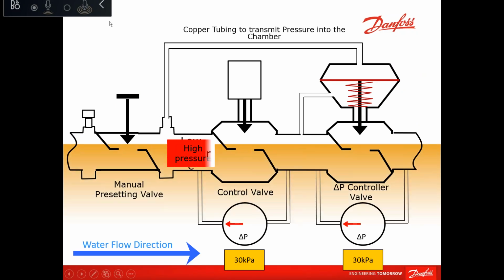And simply, what I was talking about is this part. This copper tube is linked directly with the pressure chamber. Another tube is linked with the lower pressure chamber. So if the pressure is high, it will go through here and push this part to close. Now look at the DPCV part, it's bent down. How is this done? Pressure is pushing a membrane, an EPDM membrane. The EPDM membrane is fixed on the disc. So the membrane is pushed by the pressure of the water. It will drive the disc. The disc is linked with the pressure cone of a normal two-way valve. Then it will close. So the sensing point is this tube, which is from here till this point.